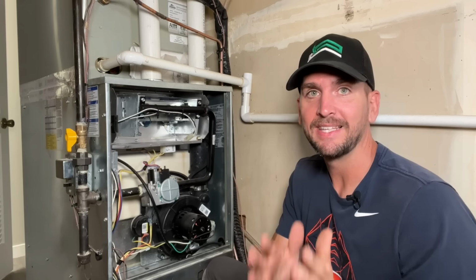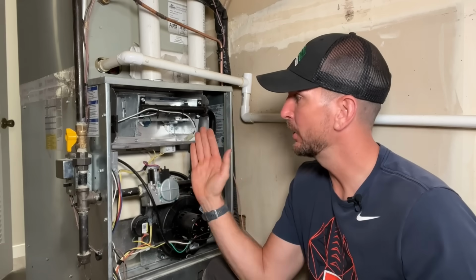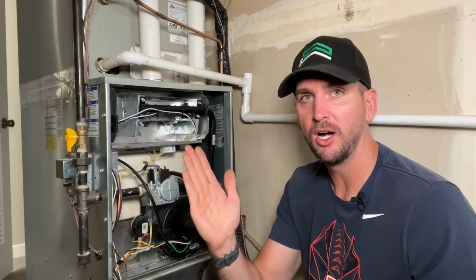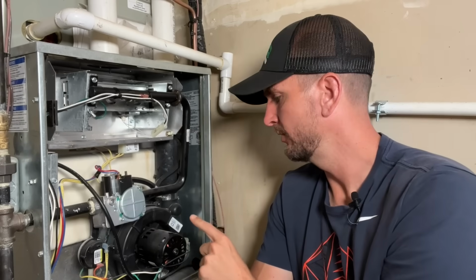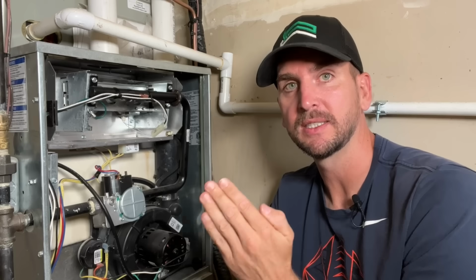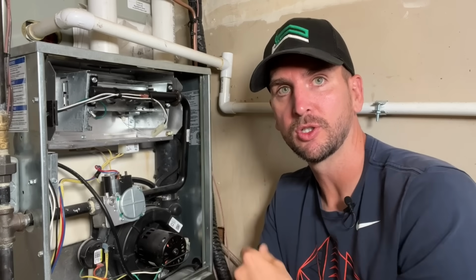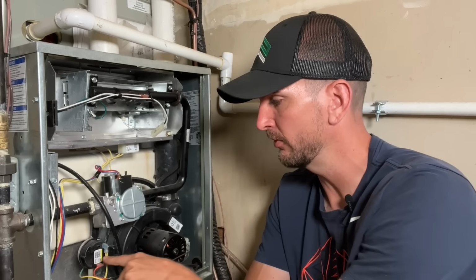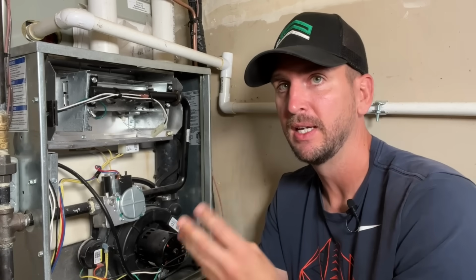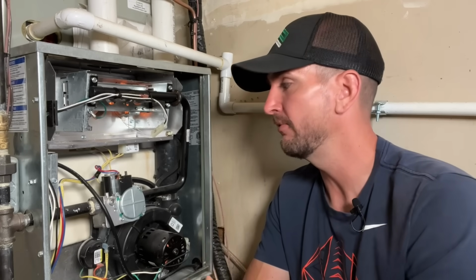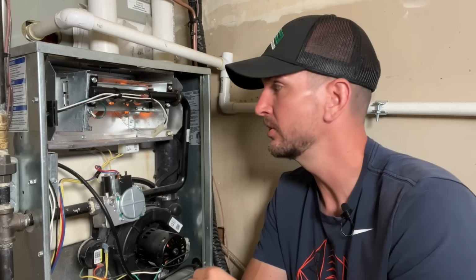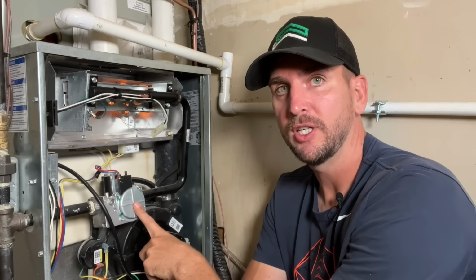But now let's look at that common failure where the burner is turning on and off and how to fix it. So on this failure mode, I just flipped on the on-off switch. We're going to go through the same steps and you'll see where the process stops. So the inducer motor turns on in step 1. Step 2, we're confirming that we have a draft. Step 3, we're going to start to glow the igniter. And then going on to step 4, the gas valve is going to turn on and try to start the burners.